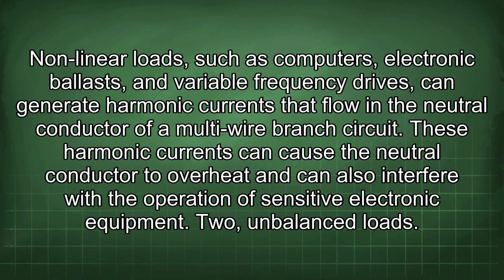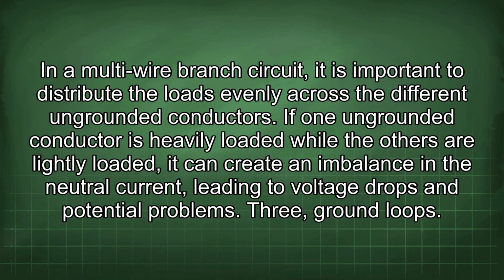2. Unbalanced loads. In a multi-wire branch circuit, it is important to distribute the loads evenly across the different ungrounded conductors. If one ungrounded conductor is heavily loaded while the others are lightly loaded, it can create an imbalance in the neutral current, leading to voltage drops and potential problems.